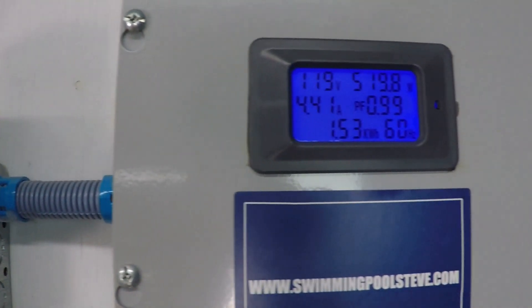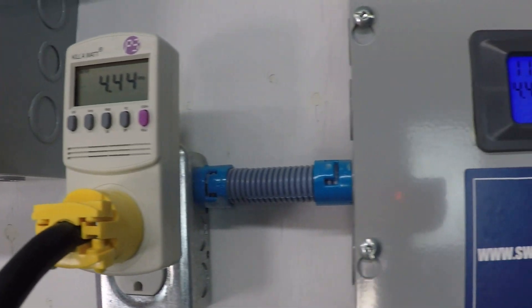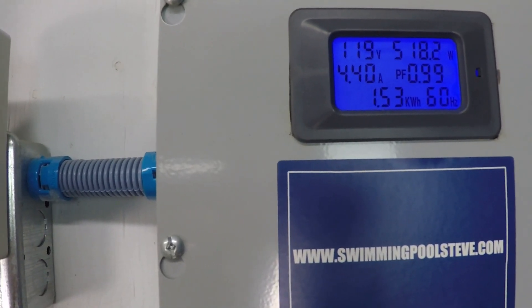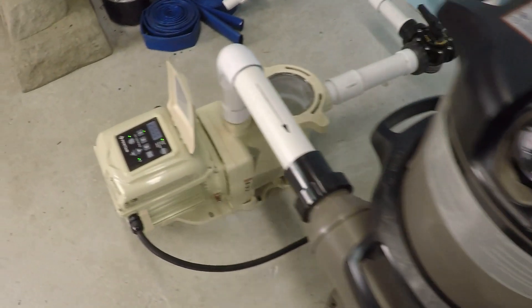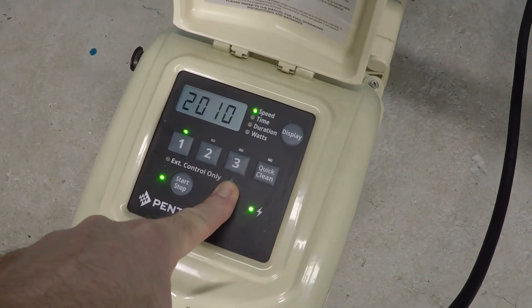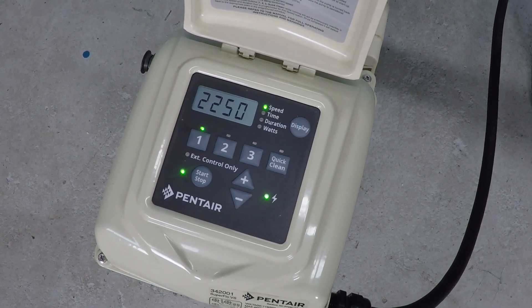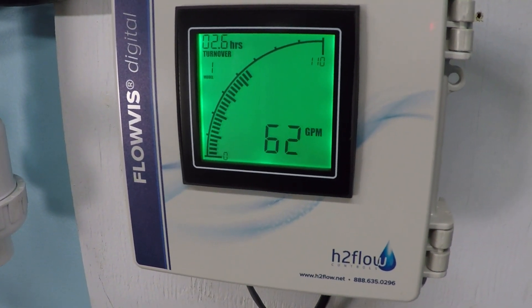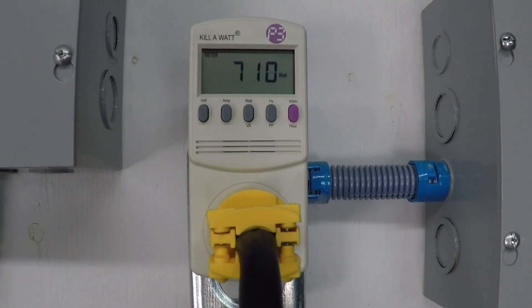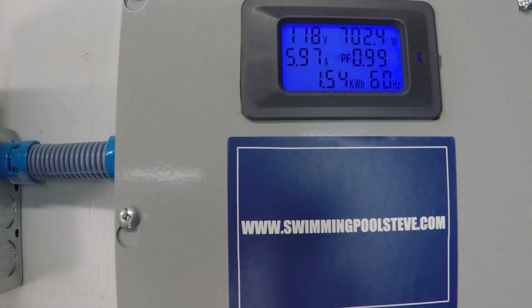Checking power consumption. 4.44 amps. Seems to be about the same. About 62 gallons per minute. 705 watts maybe. About the same over there.